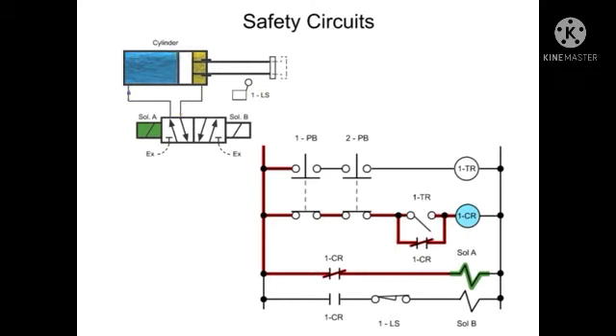At this point in the cycle, the cylinder will remain extended indefinitely until at least one push button is released. If one push button is released, the control relay will lose power, which causes 1CR to remove power from solenoid A and connect power to solenoid B.